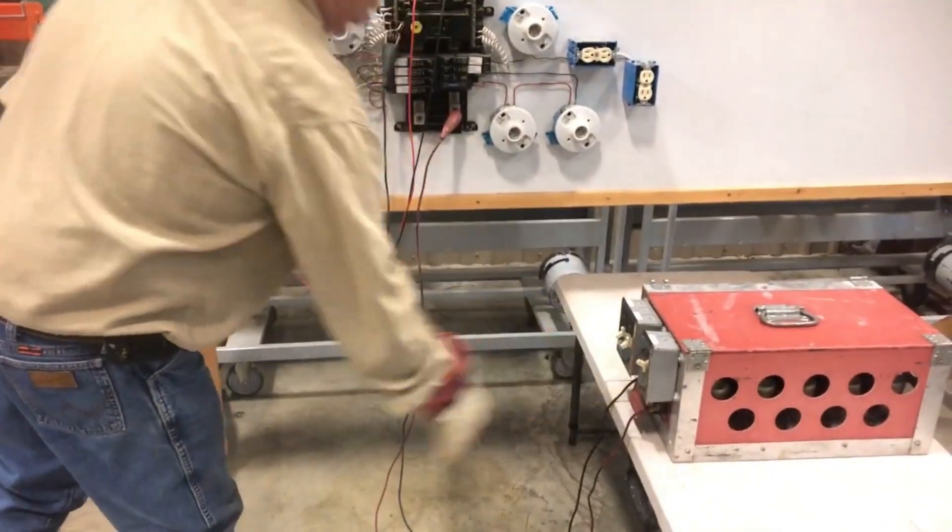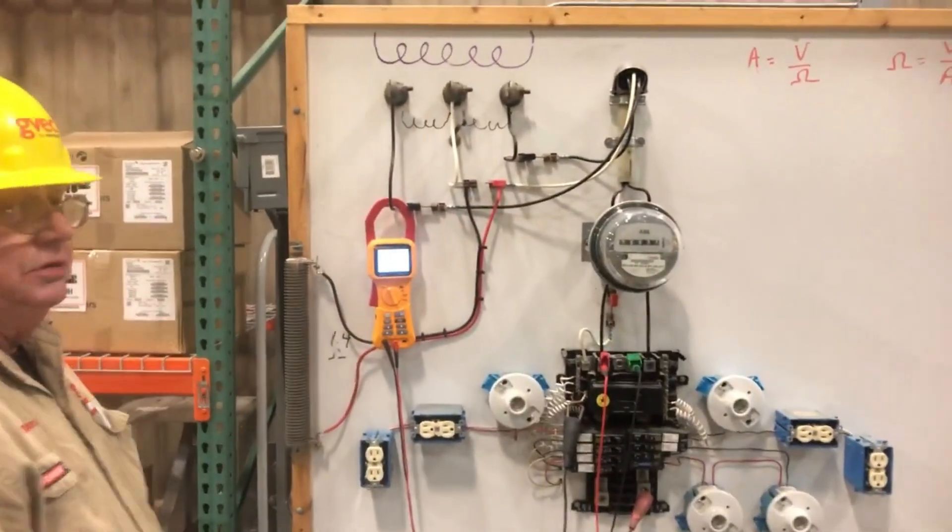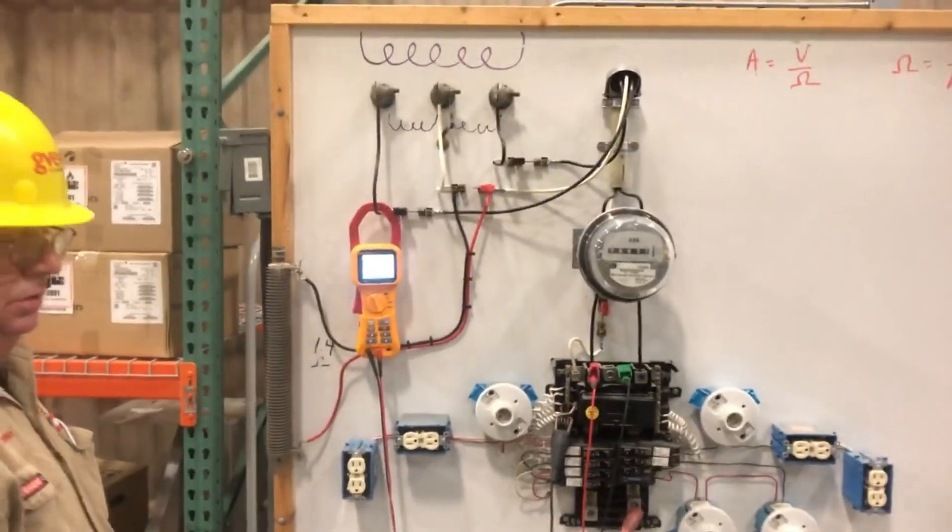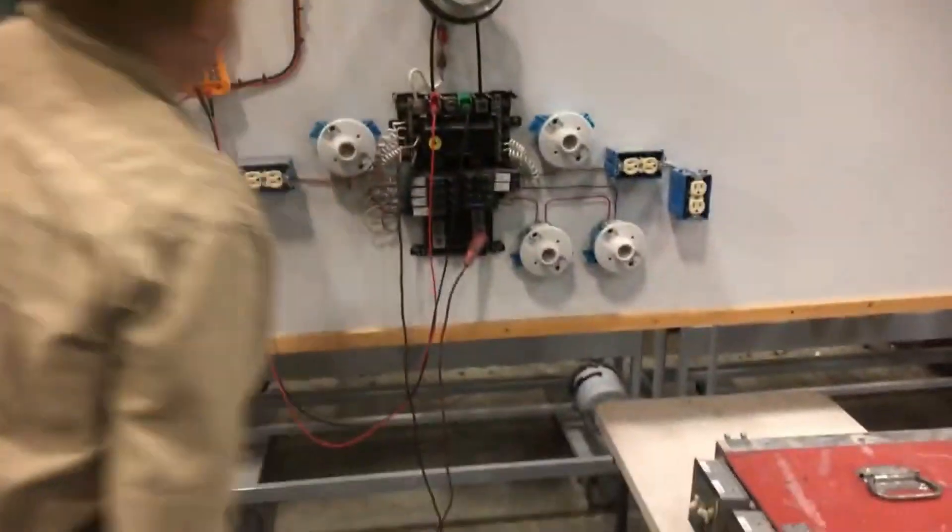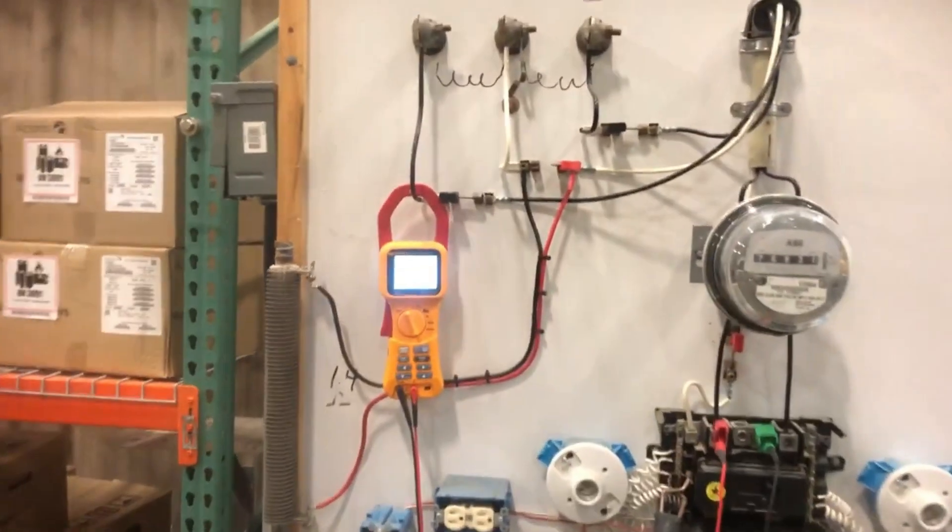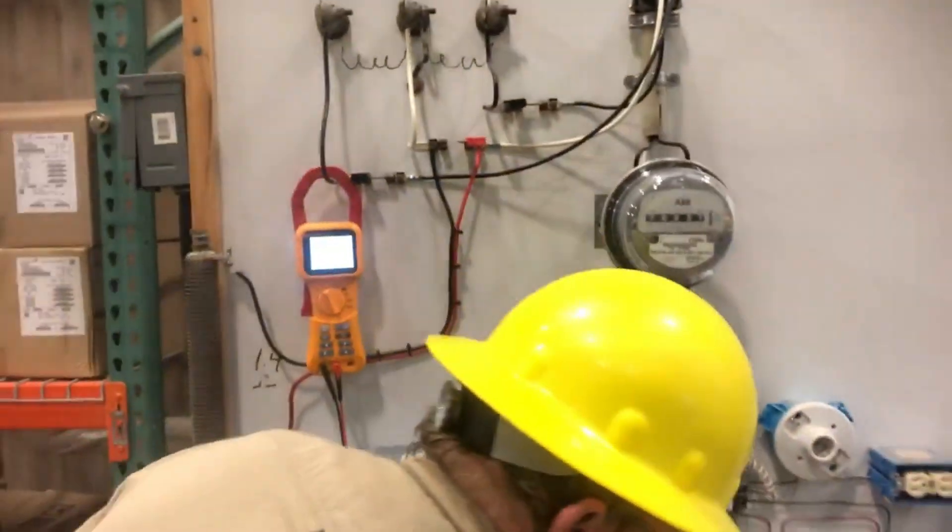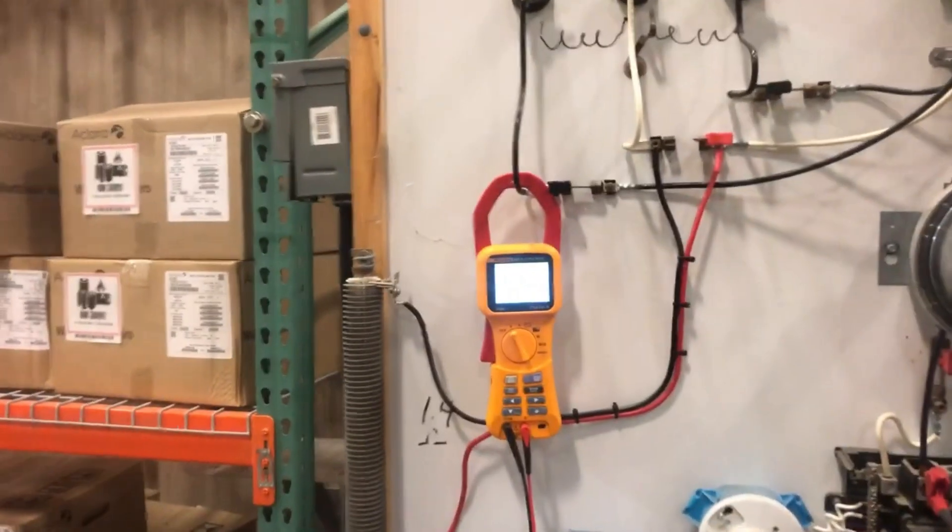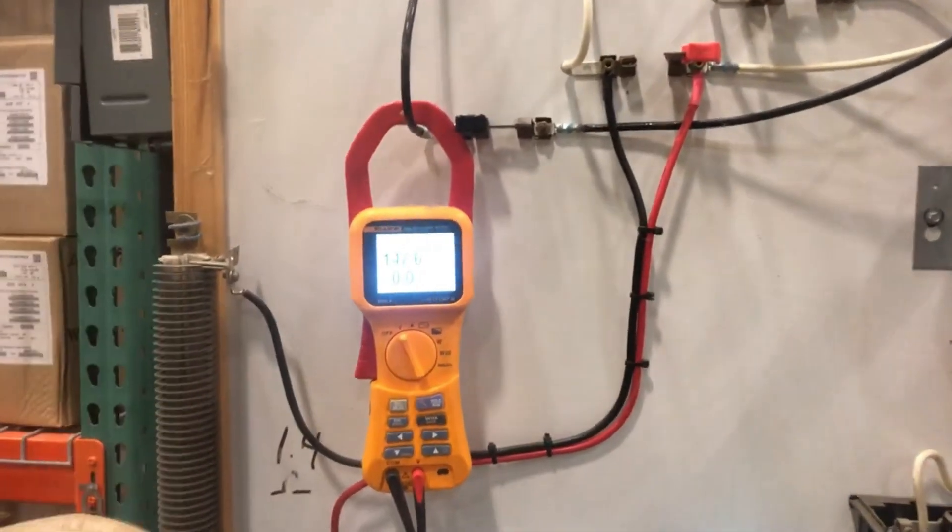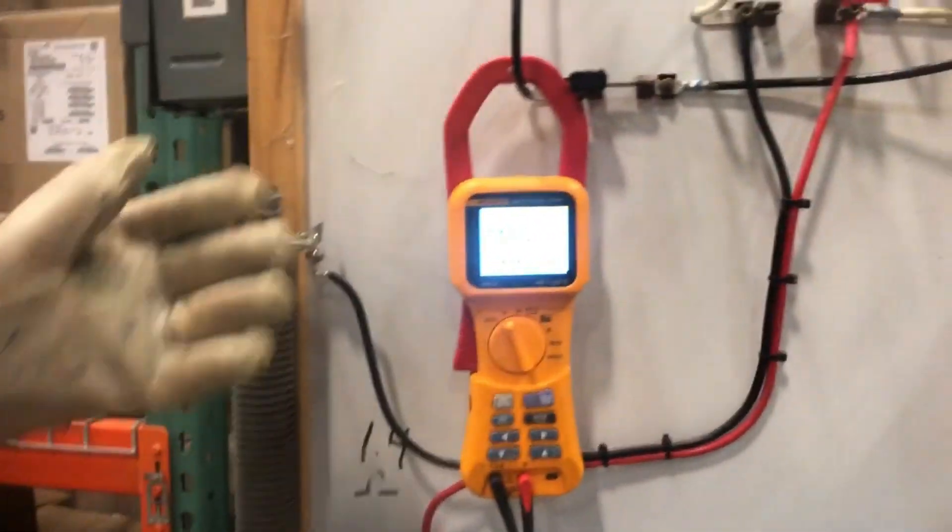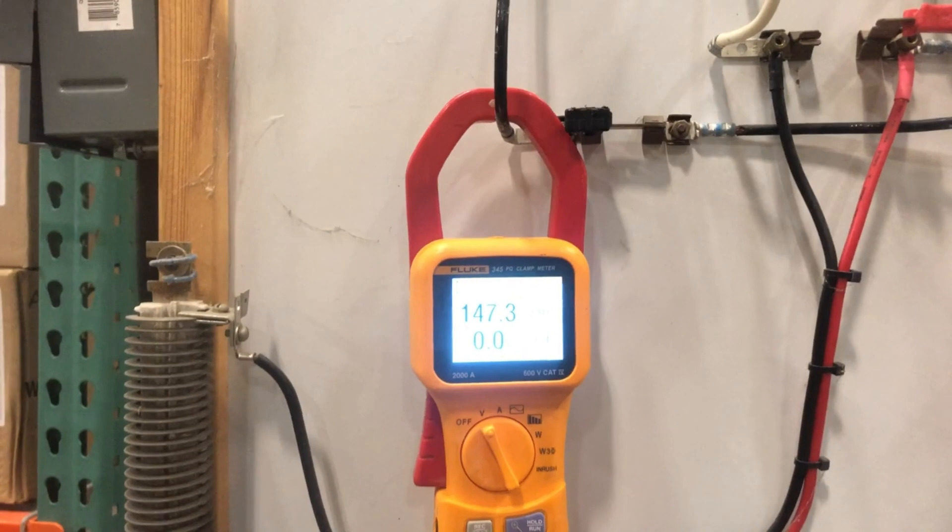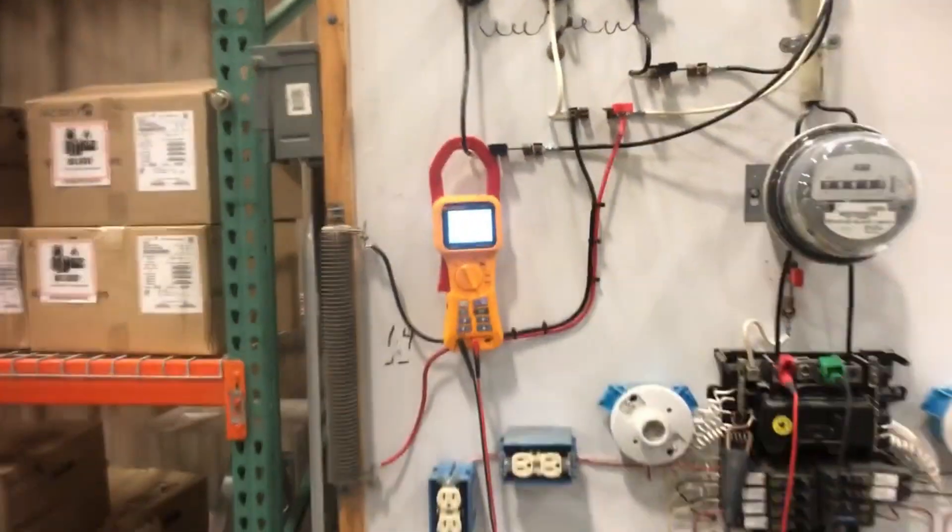We'll bring on a little bit. 7 amps. 7 amps took us to 130 volts. Now I'm going to bring in 15. I'm at 142. I'm going to bring in 24. I have 24 amps passing through this resistive connector, and our unloaded leg has risen to 147.